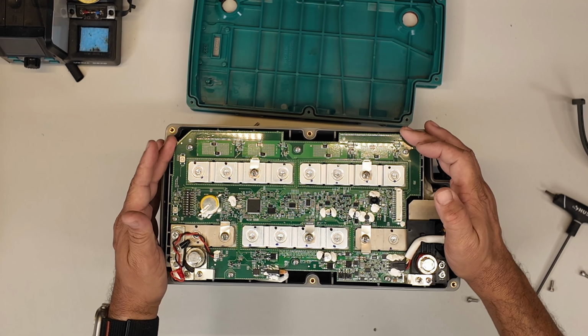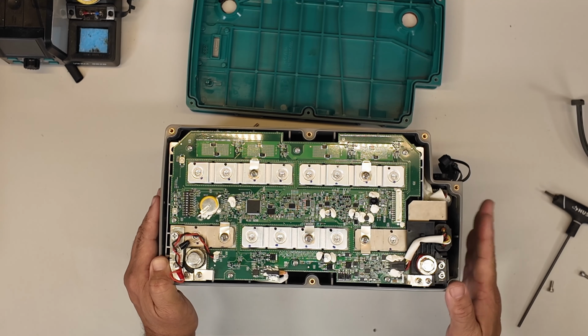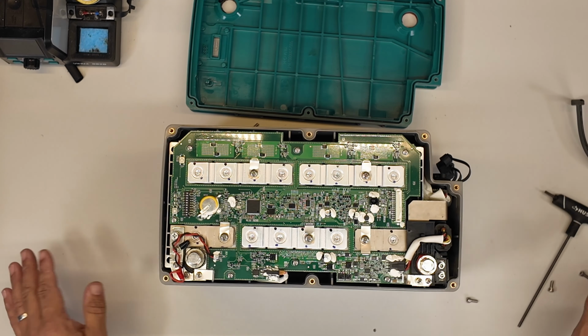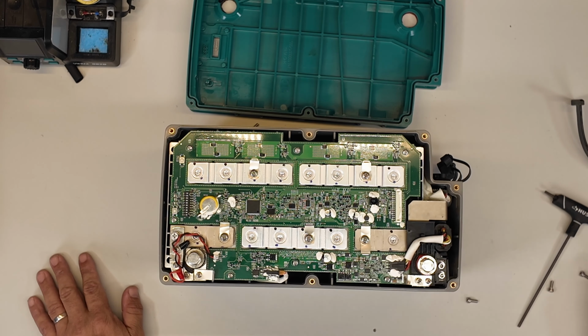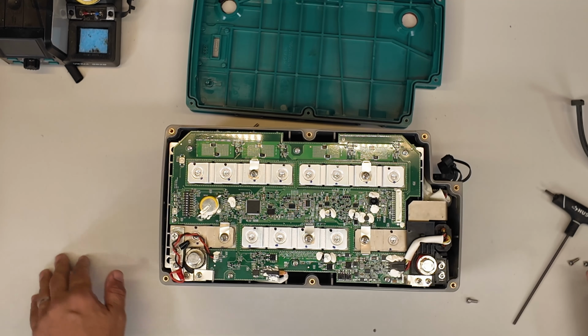It's worth noting this is not a FET-based BMS. This is a contactor-based BMS. So it's an all-on or all-off connection, but it's also a very discrete and positive control of the battery's charge and discharge. Charge and discharge are going to be controlled together because there is a single contactor controlling all aspects of the battery.